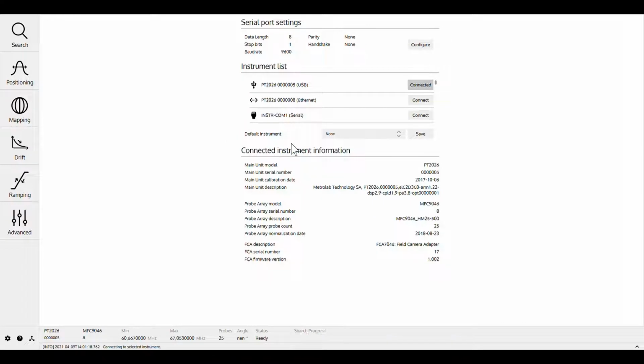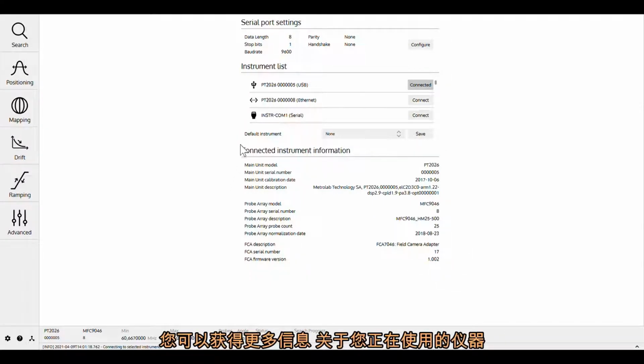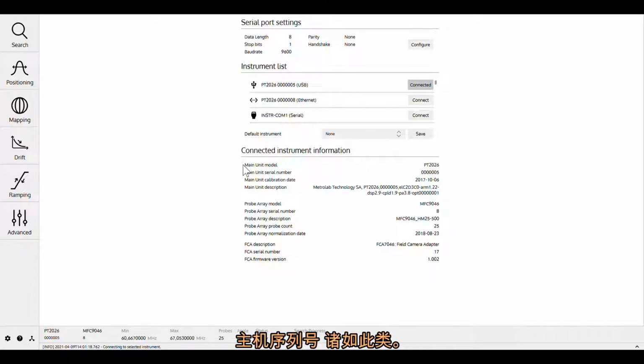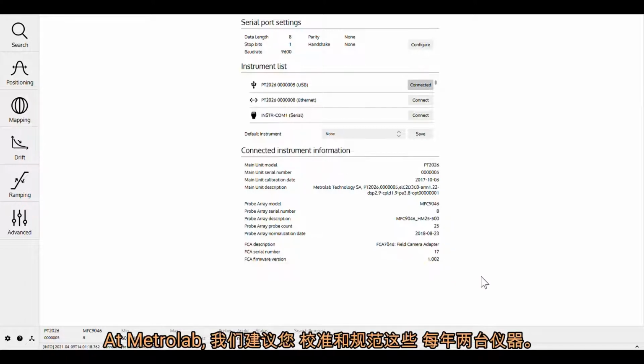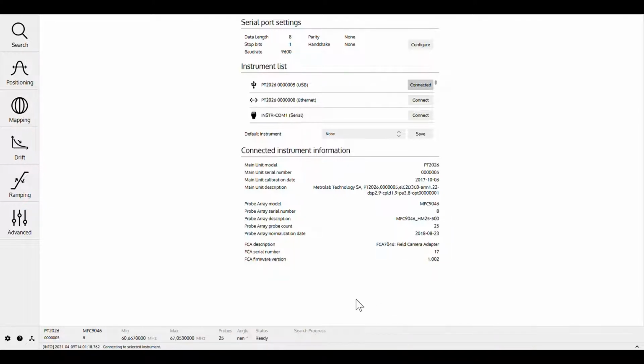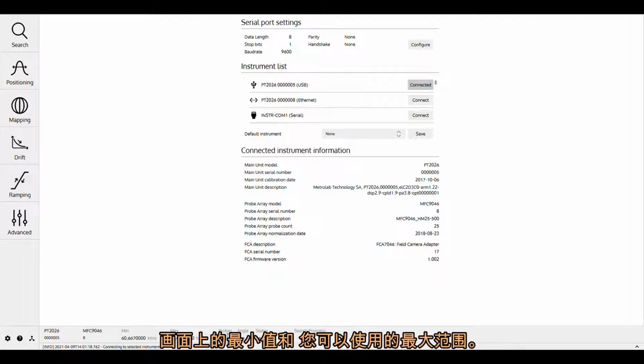Once you're connected, you have access to additional information regarding the instrument that you're using, main unit, the model, serial number, and so forth. You also have access to the last calibration date of the main unit and of the probe array. At Metrolab, we recommend that you calibrate and normalize those two instruments every year. You can also see at the bottom of the screen the value of the minimum and the maximum range that you can use, here expressed in megahertz from 60.66 up to 67.05 megahertz, which is characteristic for 1.5 Tesla probe array.